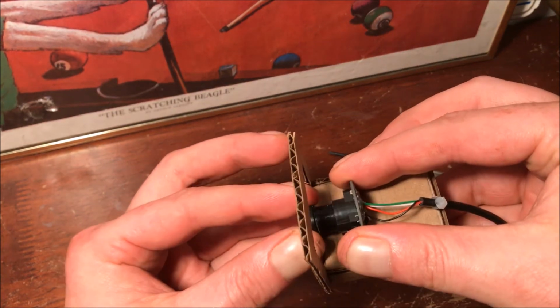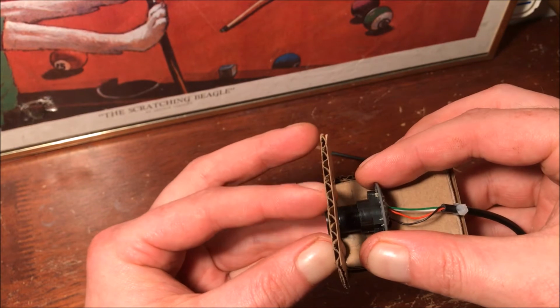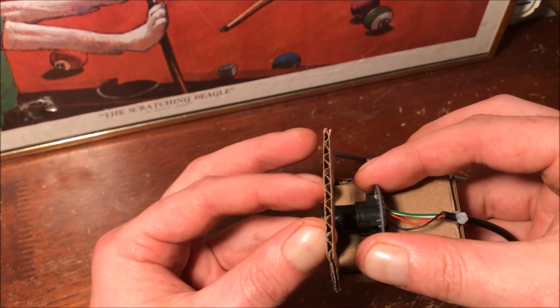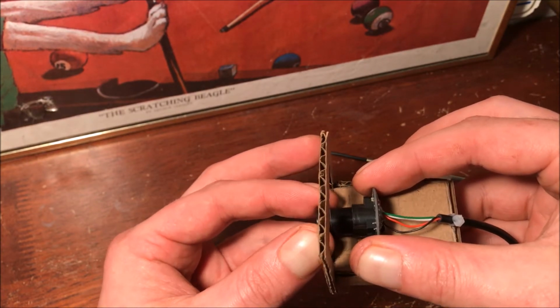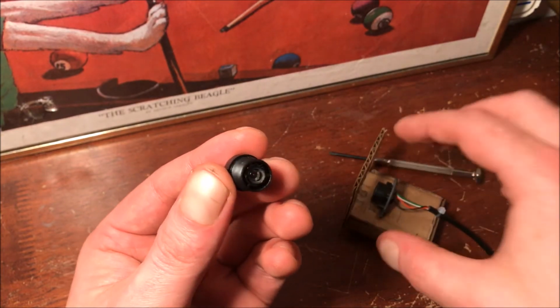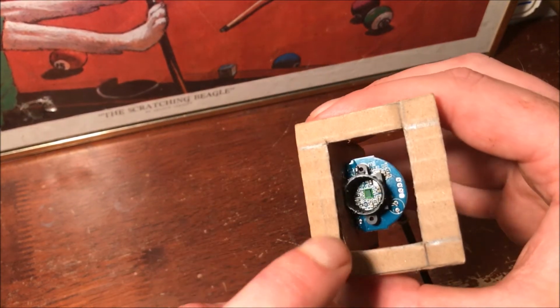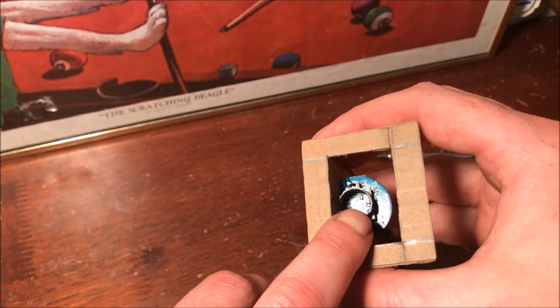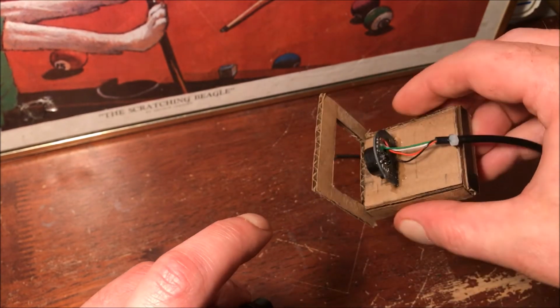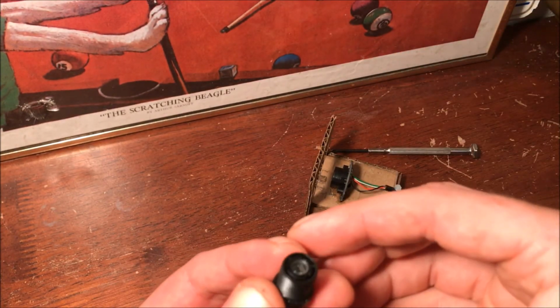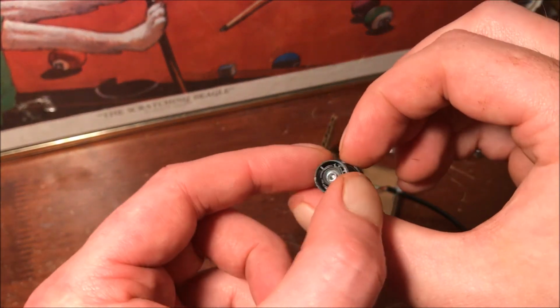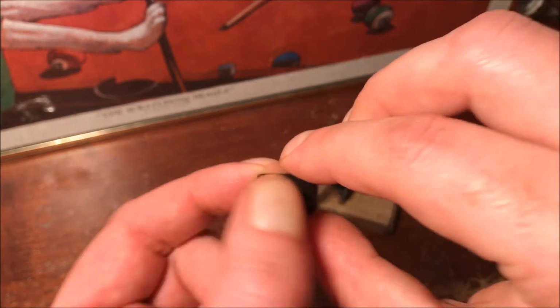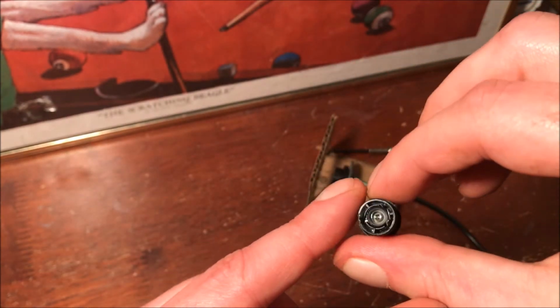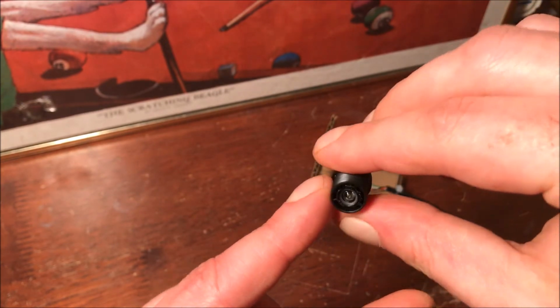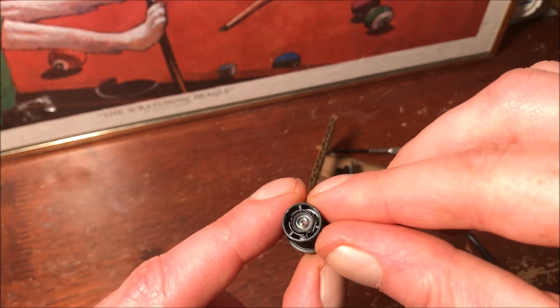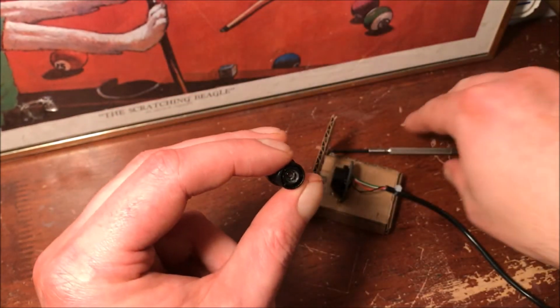And if we take out the lens on this one, and it's really going to vary on which webcam you have, they're all very similar but have slight differences. So when you take this out, you really want to be careful that nothing lands on the image sensor. Keep that really clean. And same with these lenses. I'm pretty sure these are plastic, so you could probably clean them with ethanol or IPA, but definitely not with acetone as far as solvents go.